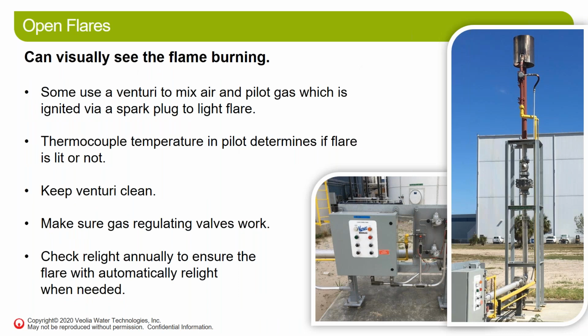So again, open flares, you can see that flame coming out of the top there. They use a Venturi to mix air and pilot gas with a spark plug to light it. So there's a thermocouple temperature in the pilot, which determines if the flare's lit or not. You've got to keep that Venturi clean, make sure the regulators are working well, check and relight the system annually at least, probably even more, just to make sure that system is functioning properly. This system, again, is a Varec picture. That's typically the manufacturer that we have supplied over the years.